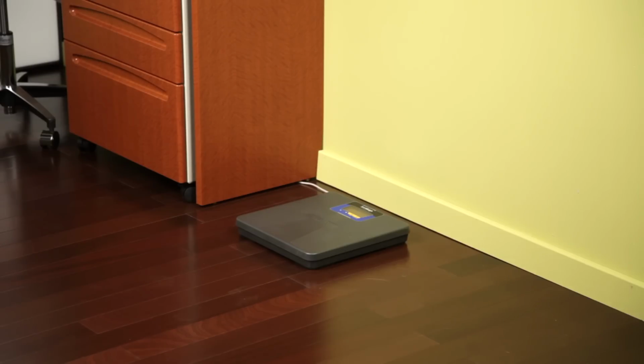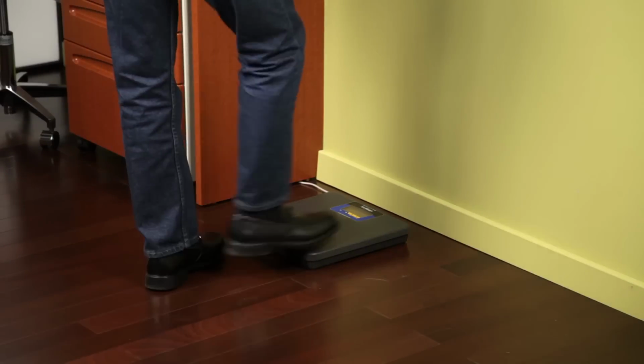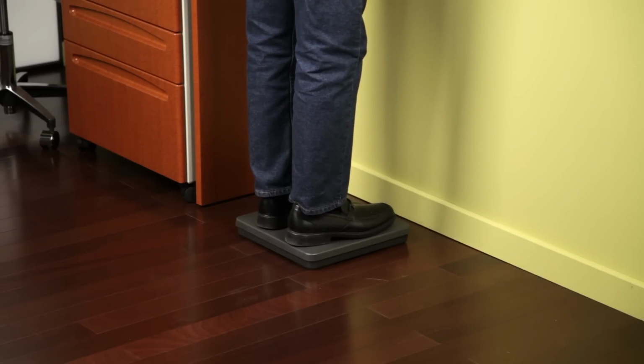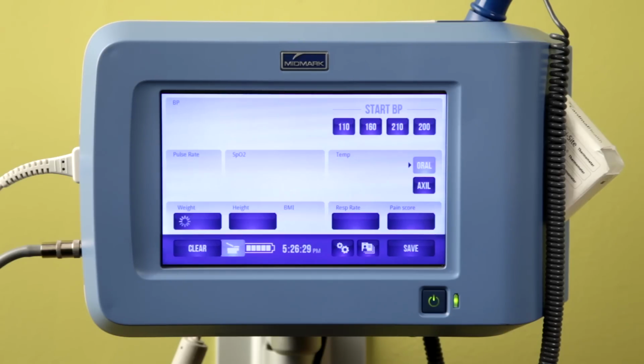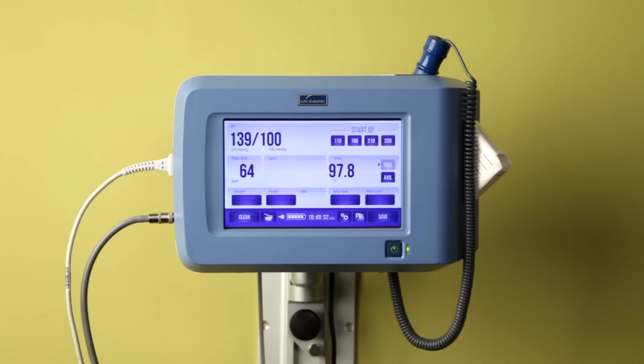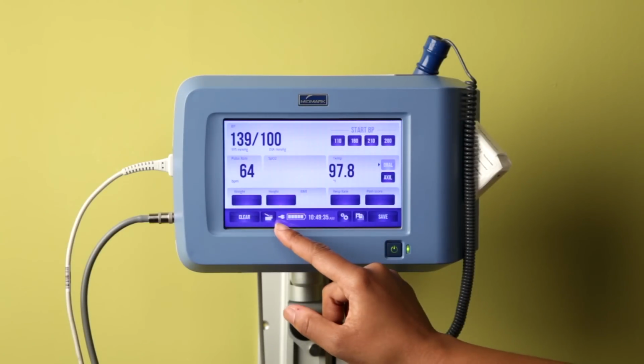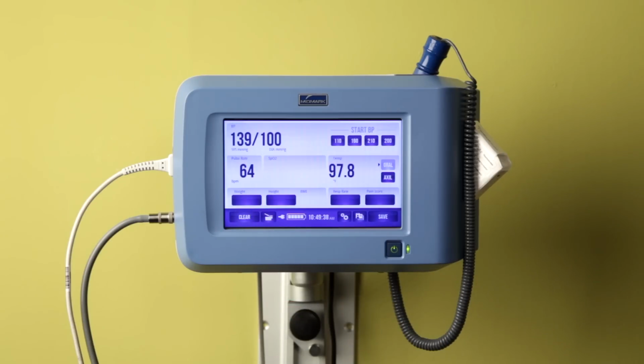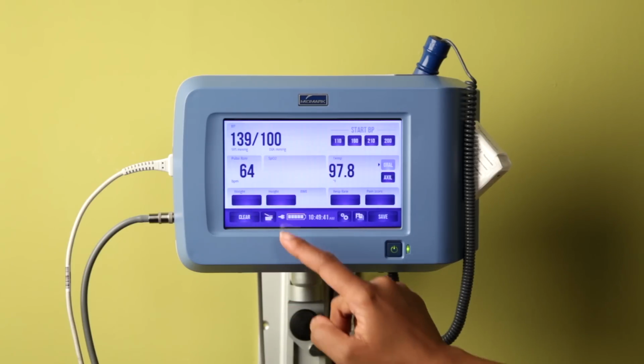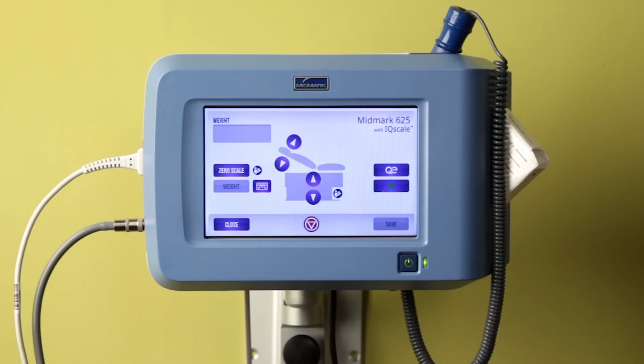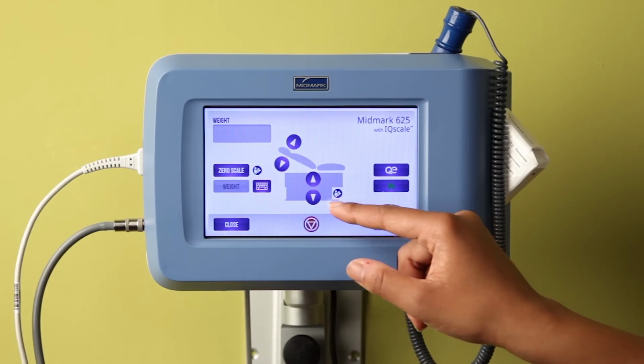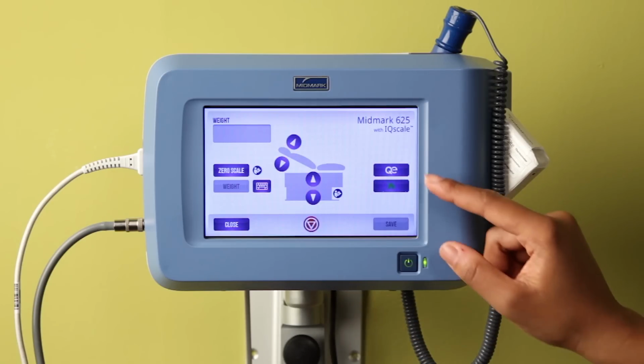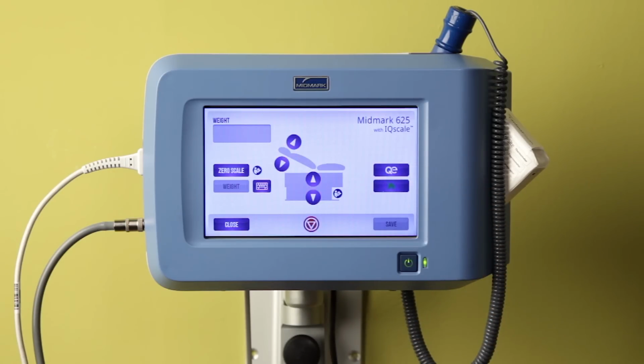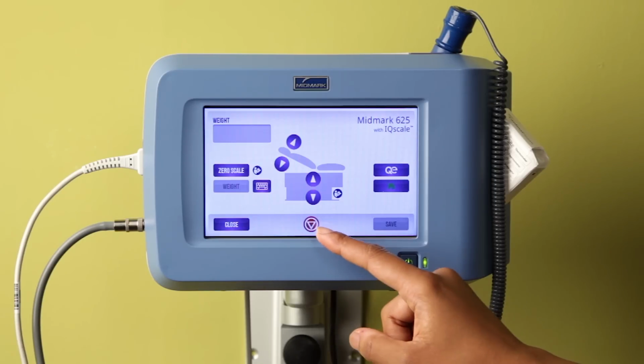A Fairbanks Tel-A-Weigh digital scale can be used for collecting patient weight. Once connected, the IQvitals device will automatically detect the scale. The scale will be ready to use and will automatically transfer the weight measurement to the IQvitals device. If connecting IQvitals to the Midmark 625 exam table with IQ Scale, the table scale button will appear to the right of the clear button on the main testing screen. If either the weight button or the table scale button is pressed, the Midmark 625 with IQ Scale screen will appear. The arrow buttons control table movement. The quick exam button sends the table to a pre-configured position, and the home button returns the table to a default position. Press the red button at any time to stop movement of the table.